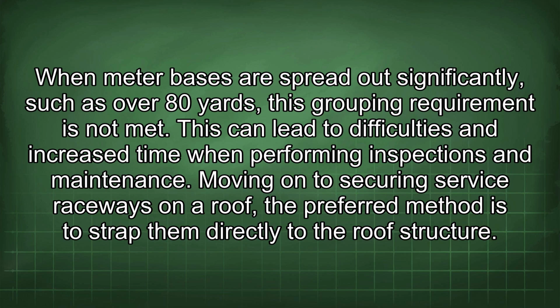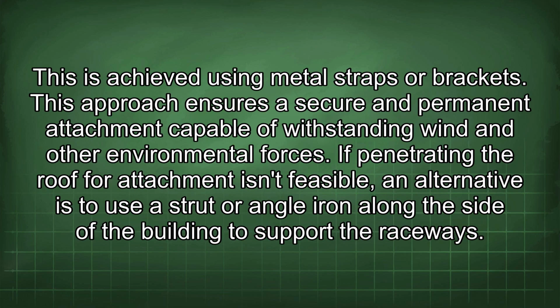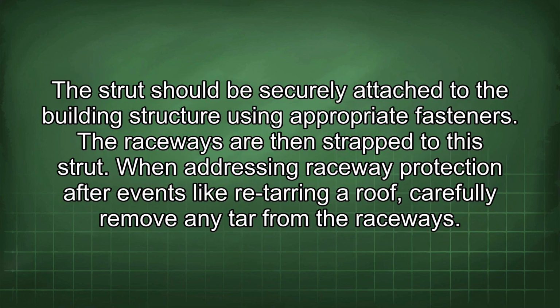Moving on to securing service raceways on a roof, the preferred method is to strap them directly to the roof structure. This is achieved using metal straps or brackets. This approach ensures a secure and permanent attachment capable of withstanding wind and other environmental forces. If penetrating the roof for attachment isn't feasible, an alternative is to use a strut or angle iron along the side of the building to support the raceways. The strut should be securely attached to the building structure using appropriate fasteners. The raceways are then strapped to this strut.